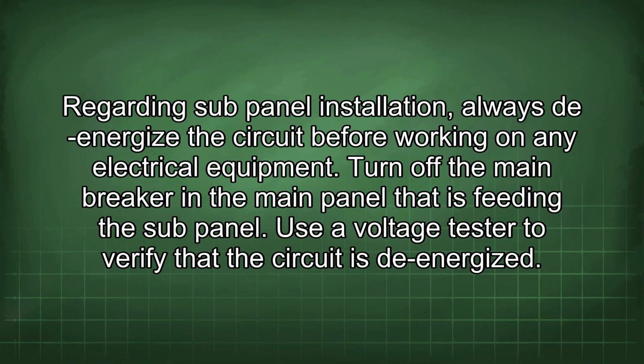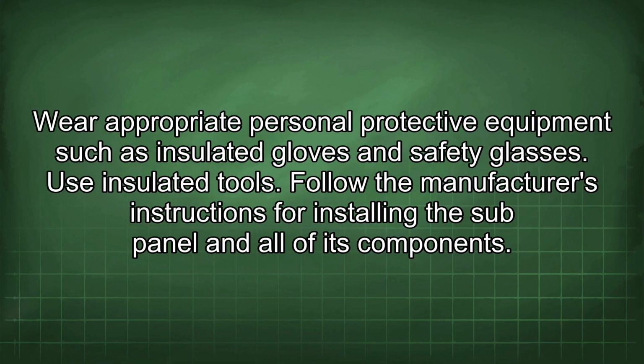Regarding sub-panel installation, always de-energize the circuit before working on any electrical equipment. Turn off the main breaker in the main panel that is feeding the sub-panel. Use a voltage tester to verify that the circuit is de-energized. Wear appropriate personal protective equipment such as insulated gloves and safety glasses. Use insulated tools. Follow the manufacturer's instructions for installing the sub-panel and all of its components.